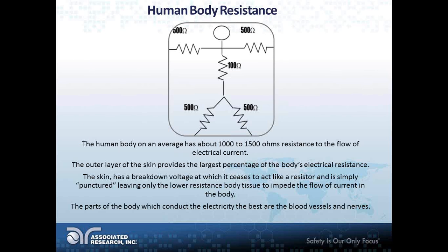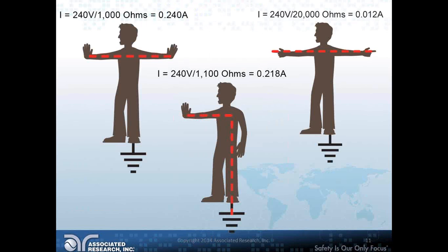Let's look at a couple of examples, some models of different contact points. I said 1,000 to 1,500 ohms—let's just assume 1,000. That range assumes a very large contact area. If you look at the Abe Lincoln figure in the upper left, that represents full hand-to-hand contact, like wrapping both hands around a conductor the size of a Coke can in each hand—that's a lot of contact area. That's really when you're talking about the 1,000 to 1,500 ohm range. If you actually measured it, it might even be more than that, but I like these conservative estimates.